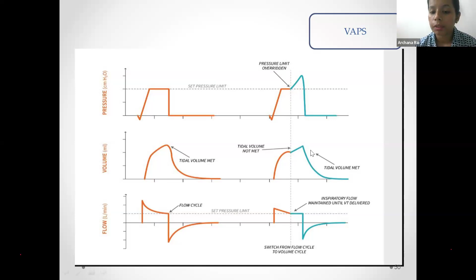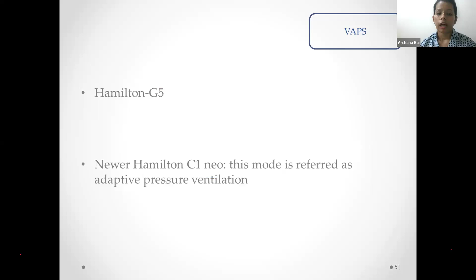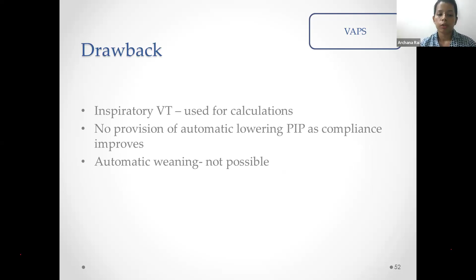So to achieve the tidal volume, it will increase the pressure limit, and it will keep the inspiratory flow maintained till the time a tidal volume has been reached. Once the tidal volume has been reached, the cycle will go into the expiratory phase. So it is in Hamilton ventilators. The drawback is that inspiratory VT is usually used and automatic weaning is not possible.